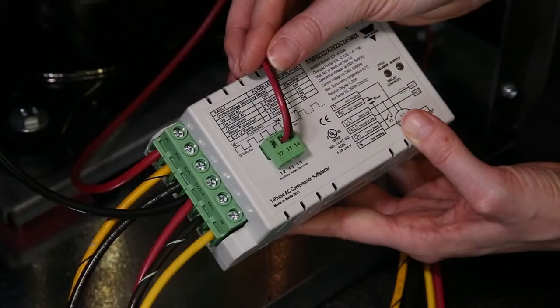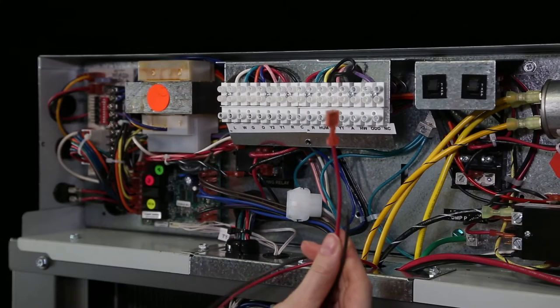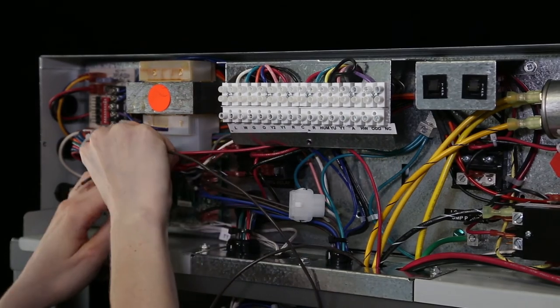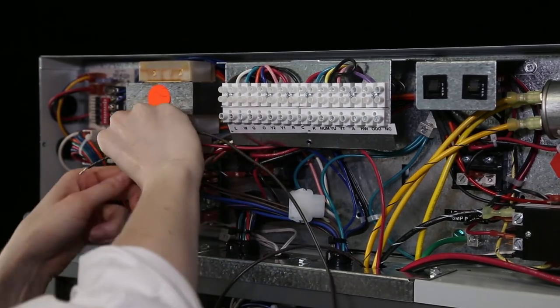Connect one end of the red 18 gauge wire to terminal 11 on the auxiliary relay connector on the soft start module and the other end to the R1 terminal on the top right corner of the lockout board.